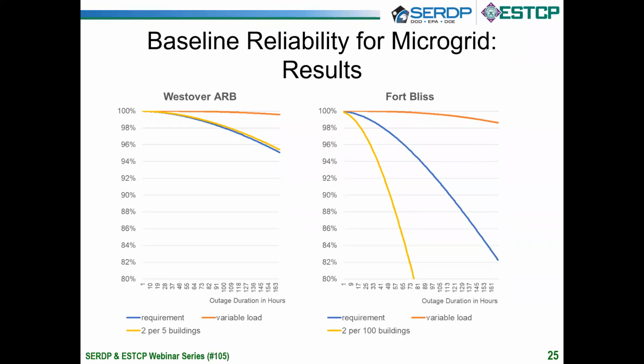Not shown on this chart is what would happen if you had only a single generator tied to each building, because that would be even worse and would fall off within the first half a day to below visibility. Similar results are shown for a small base, in this case, Westover Air Reserve Base. In that case, because the number of buildings is relatively small, the difference between an N+1 microgrid and 2 generators per 5 buildings is very similar. And again, remember, that's the minimum performance we are saying must be met for satisfying the military requirements.